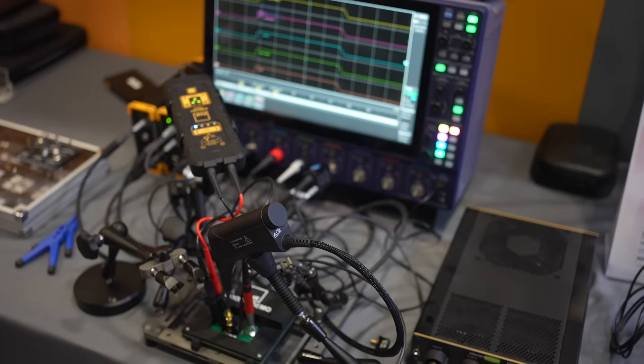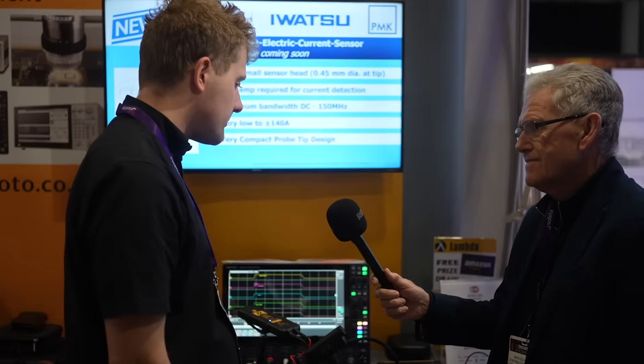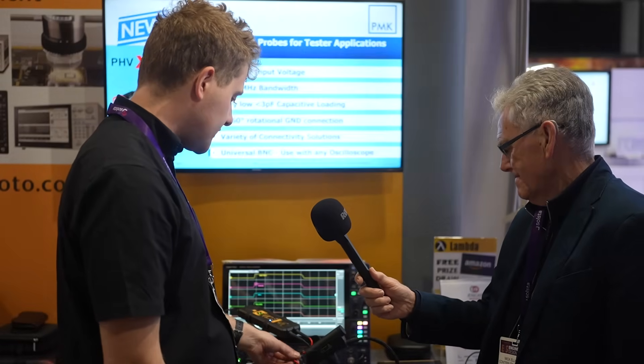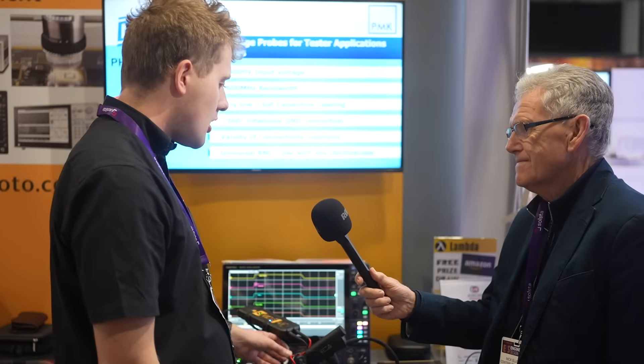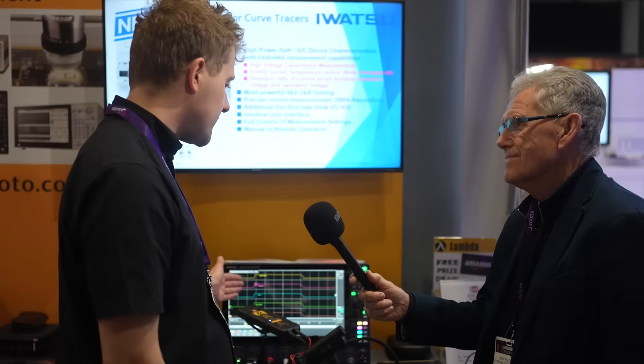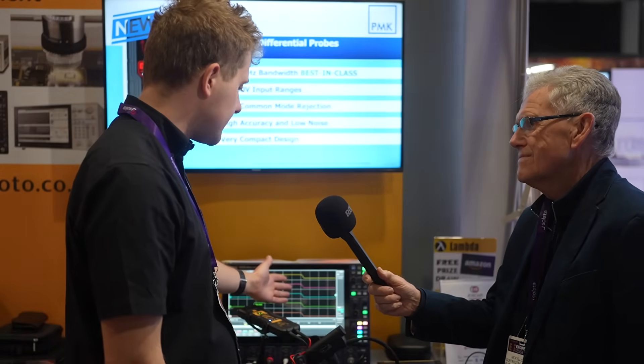Here we are measuring the same signal, which is a very high-speed pulser, with a variety of different probes. On these probes we have adapters, cables and wires. On the signal you can see that the adapter cables are adding some ringing on a signal less than 1 nanosecond. On a signal more than 4 nanoseconds, all of the probes measure correctly.